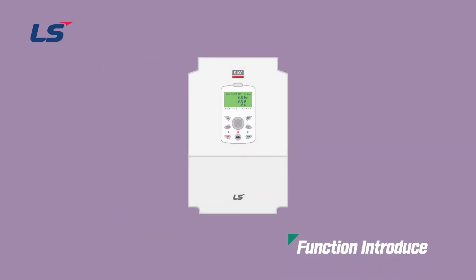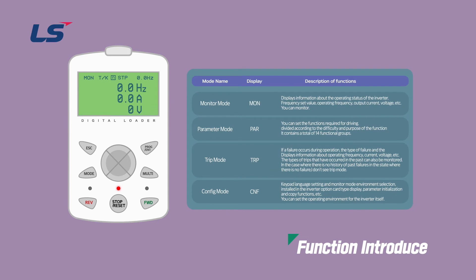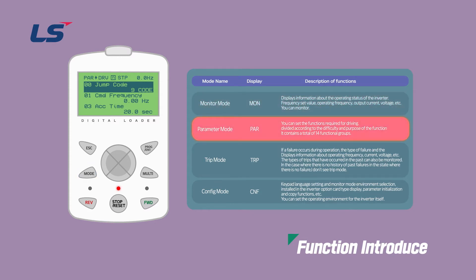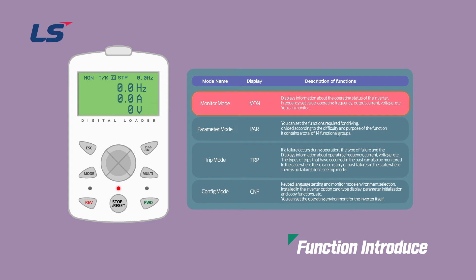First, let's talk about the digital loader. The digital loader is connected to an S100 inverter and has four modes. If you click the mode key in monitor mode, the parameter mode appears. If you click the mode key again, the configuration mode appears, and if you click the mode key again, you can see that it returns to the monitor mode. However, the trip mode can be moved if there is a previous trip history.